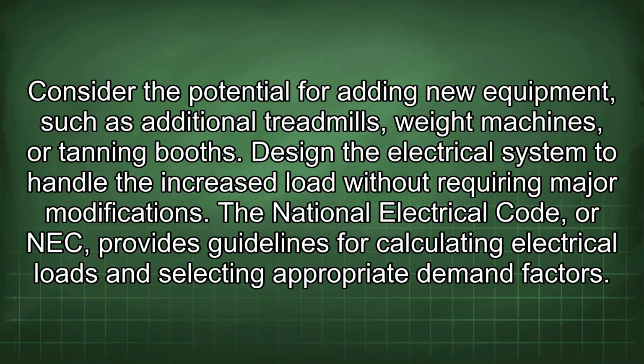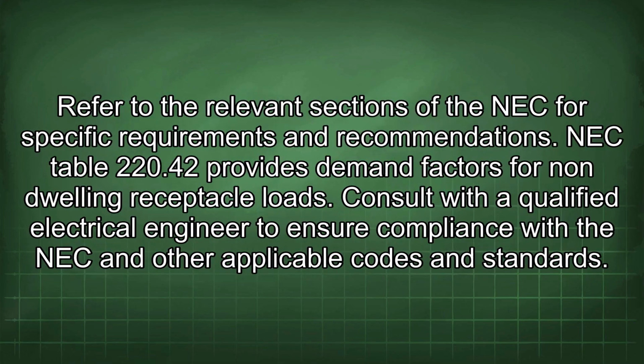The National Electrical Code, or NEC, provides guidelines for calculating electrical loads and selecting appropriate demand factors. Refer to the relevant sections of the NEC for specific requirements and recommendations. NEC Table 220.42 provides demand factors for non-dwelling receptacle loads. Consult with a qualified electrical engineer to ensure compliance with the NEC and other applicable codes and standards.